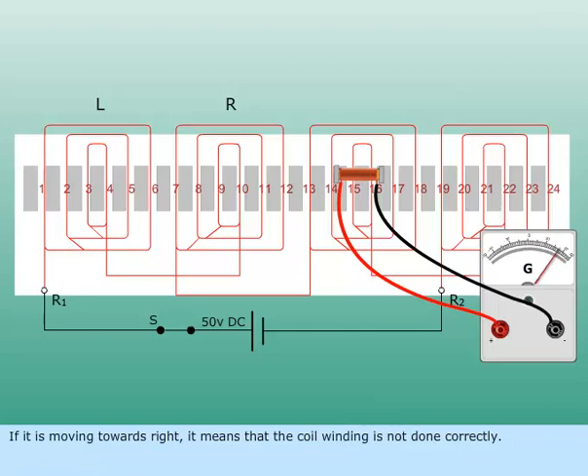If it is moving towards right, it means that the coil winding is not done correctly. Necessary corrections have to be done or you will have to rewind the motor.